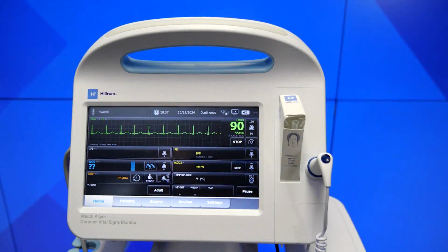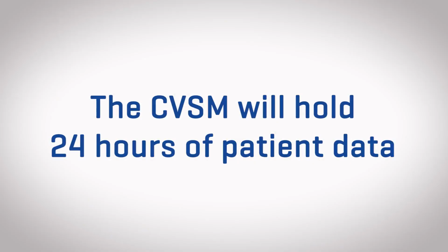When any measurements fall outside of alarm limits, all continuous measurements are saved. NIBP and predictive temperature measurements are saved when acquired. Manual parameters are saved when you touch OK on the Manual tab. Modifiers are set when you complete parameter setup and return to the Home tab. These modifiers do not appear on the Review tab.